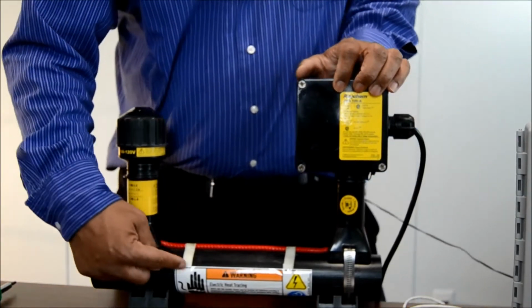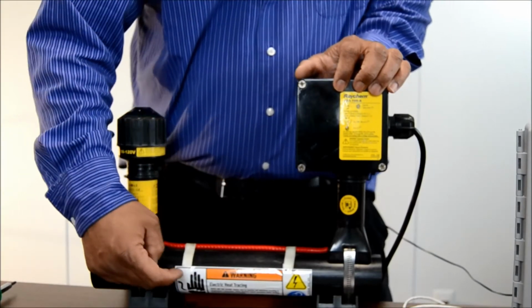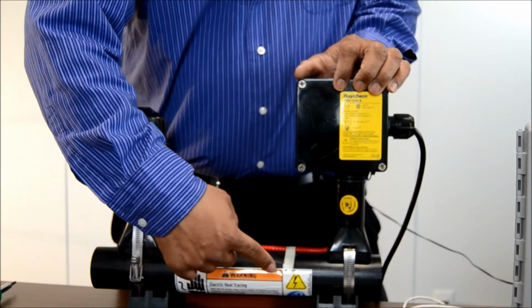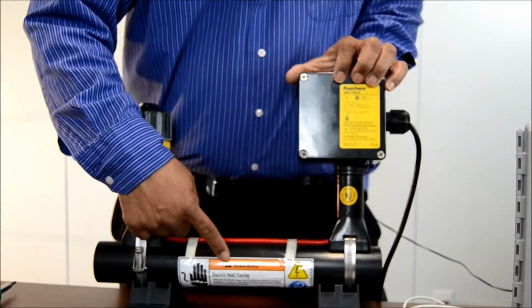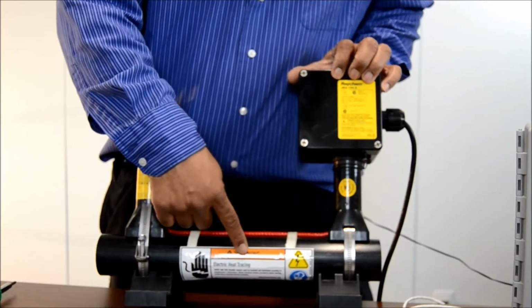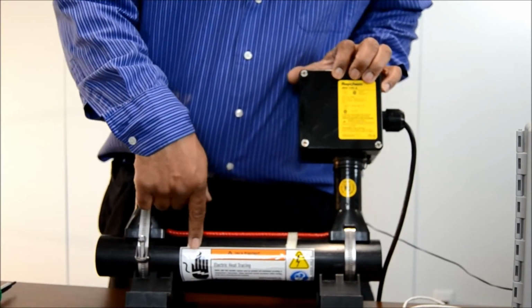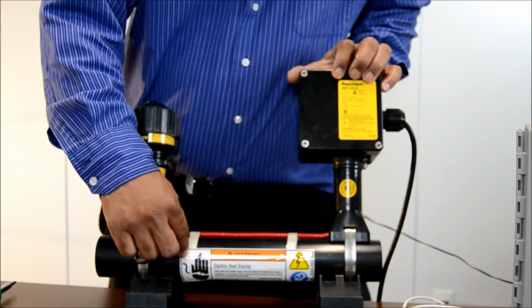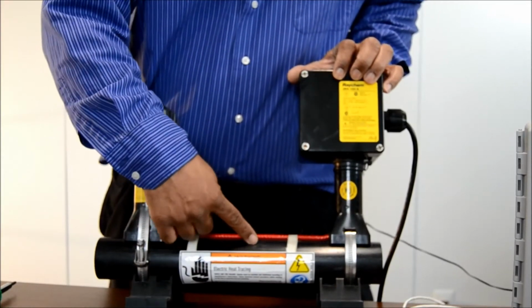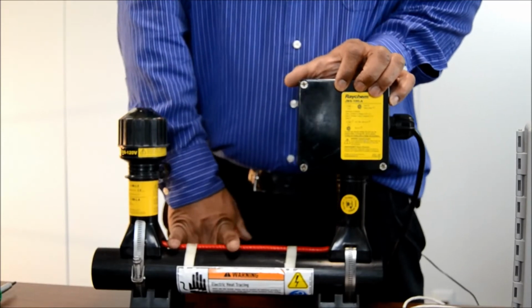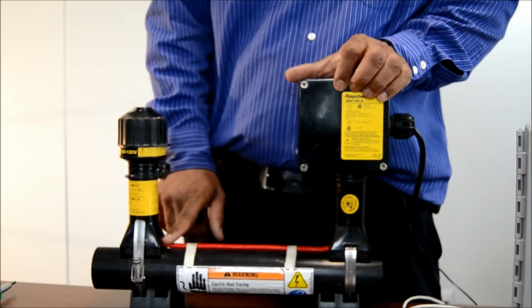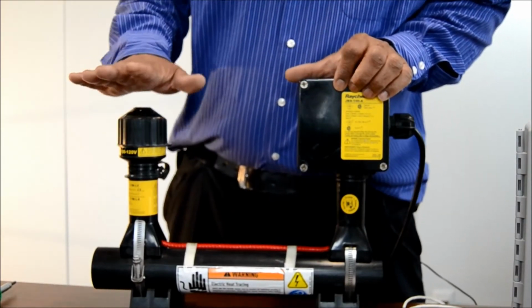Another inconsistency with this particular diagram that wouldn't be out in the field is this label right here. This is a warning label showing everyone that heat traces below the insulation. So this label would actually go above the insulation after the heat trace is installed. And always at the end of the circuit, you have an end seal.